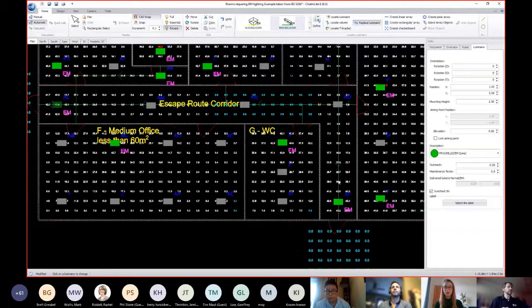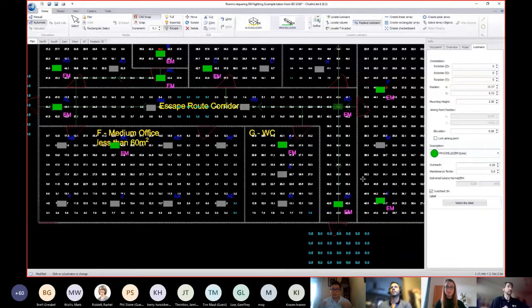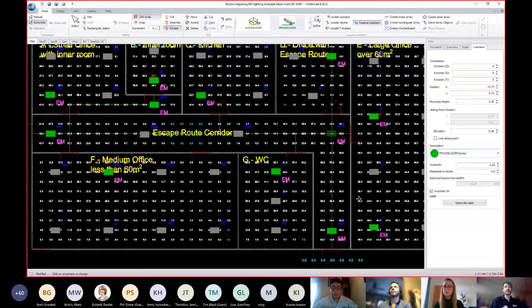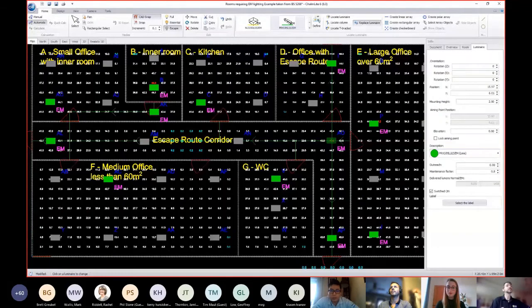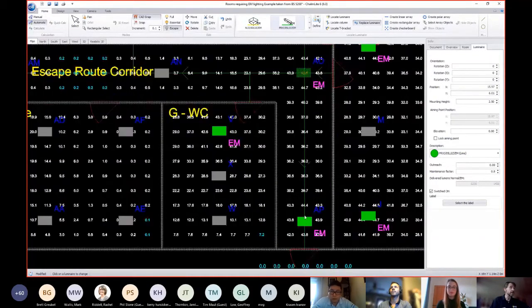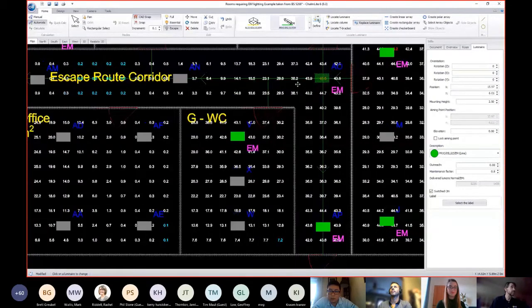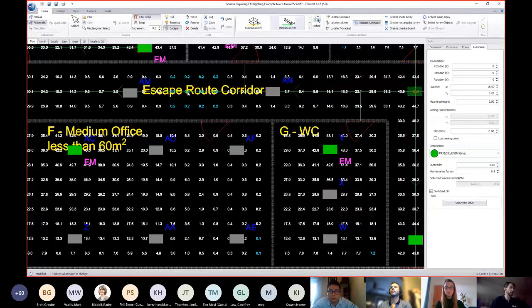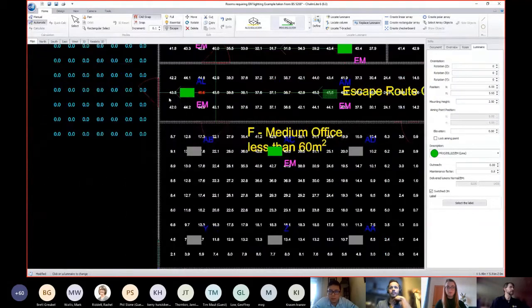Changes of direction. We've got a corridor here. We've got a change of direction. So this thing here has got to be an emergency. Okay, hopefully we're building up a nice picture of emergency fittings here. The next part is we've got to connect up our emergency luminaires so we can achieve our one lux down the centre line. So we can see our centre line here. We've got excessive lighting as we move along. Oh dear, we've fallen below 1 lux. So what we're going to have to do is make another fitting emergency so that all the lighting levels directly across the escape route are more than 1 lux.